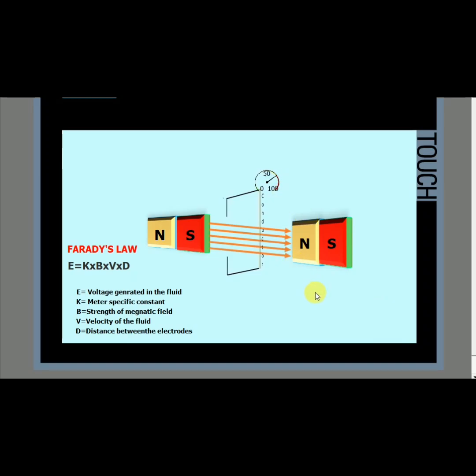Faraday's law can be expressed simply as E is proportional to K times B times V times D, where E is the voltage generated in the fluid. K is the meter specific constant. B is the strength of the magnetic field. V is the velocity of the fluid. D is the distance between the mag meter's electrodes.